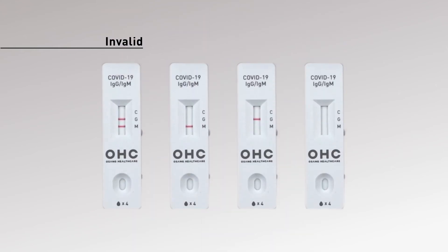If the control line is partially red and fails to completely appear in the control line region, insufficient specimen volume or incorrect procedure techniques are the most likely reason for control line failure. Review the procedure and repeat the test with a new test cassette. If the problem persists, discontinue using the test cassette immediately and contact your local distributor.